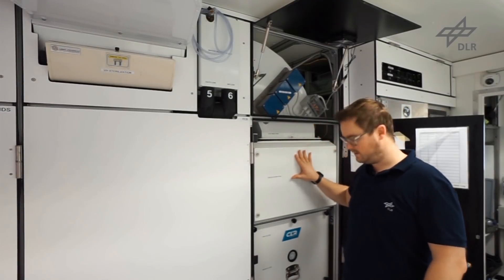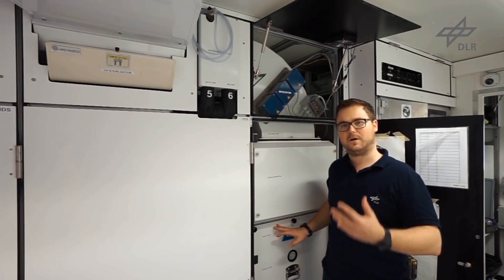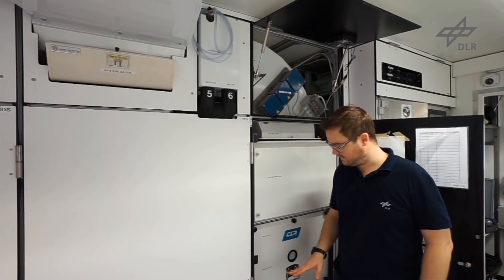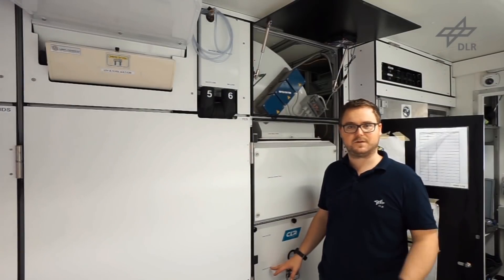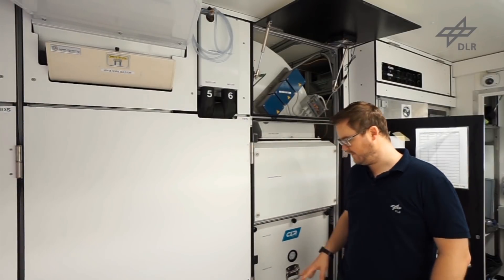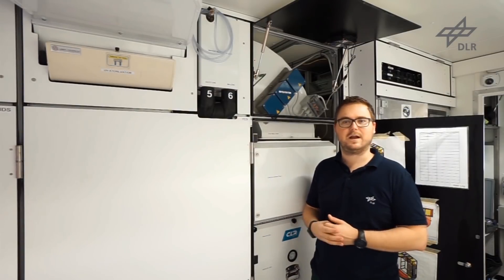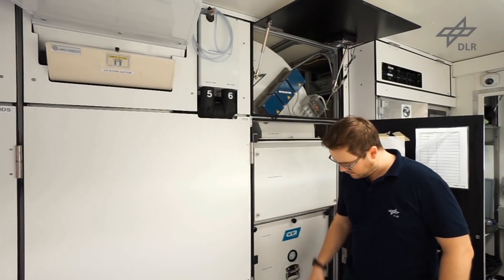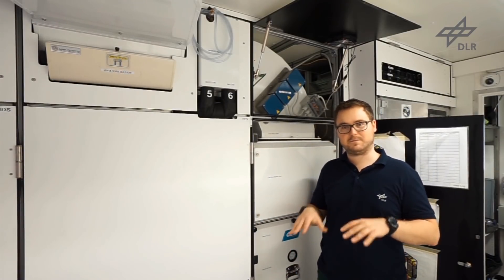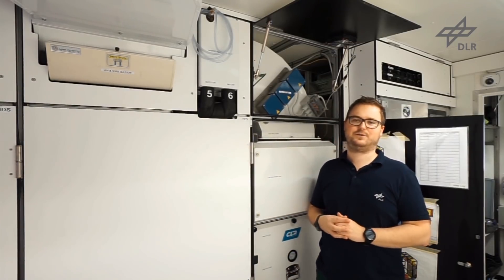Here is a big fan. There are three different kinds of filters: a pre-filter for any large particles, a HEPA filter to filter out bacteria and contaminations, and a trace gas filter with active charcoal that filters out different volatile organic compounds that are in the air. Below that is another fan, and then via subfloor ducts beneath the floor, the air is pumped back into the greenhouse.